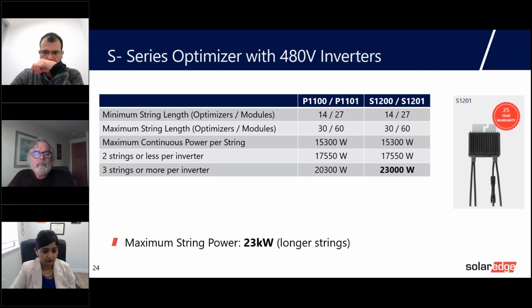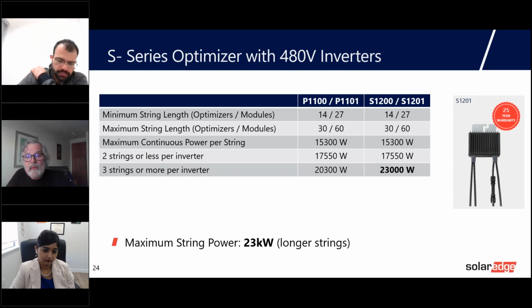And then again, with three strings, now the inverter is going to be limiting total string current. We're comfortable with much more oversizing. So 20.3 for the P1100 series, and then a little bit higher for the S1200, S1201 at 23 kilowatts. And next slide, please.